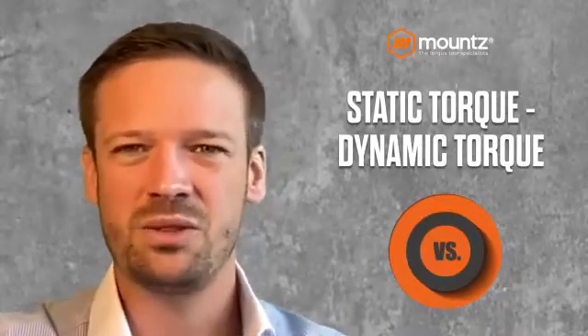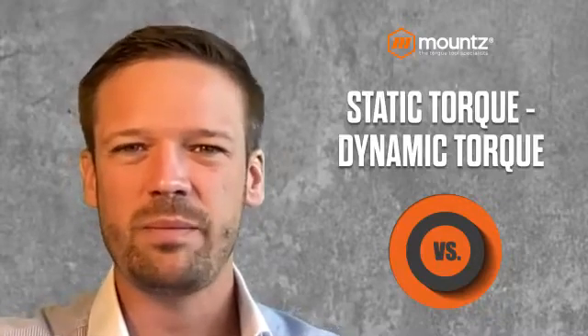There are two main ways of measuring torque: static and dynamic torque measurement. Static measurement is basically a reaction measurement. We use static sensors to check the torque output of the tool. Whereas with dynamic torque measurement, it's a dynamic version of measuring the torque of the tool, and this allows us to take into consideration different variables that are important when checking torque tools.